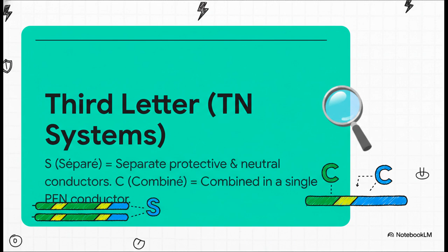And sometimes you'll even see a third letter, but only if it's a TN system. An S stands for séparé, which means separate - you have a separate safety wire and a separate neutral wire. And a C stands for combiné, which means they're combined into one single wire for part of the journey.